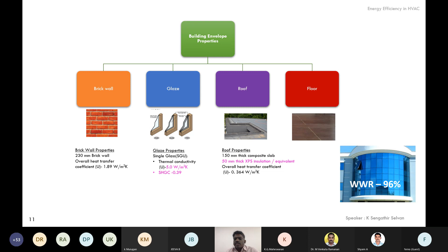So now here you can see. In this case, in a base case we consider a normal brick wall, and single glaze fenestration, and in the roof we consider a normal concrete slab, and a regular floor. And here we have considered 50 mm thick XPS insulation or any equal insulation as an underdeck insulation for the roof. This is mainly to avoid the radiation heat getting in. So now you can see with the base case we have done the calculations. You can see the envelope load itself is around 32%. I mean, envelope load means your load due to your fenestration and wall and roof and floor.